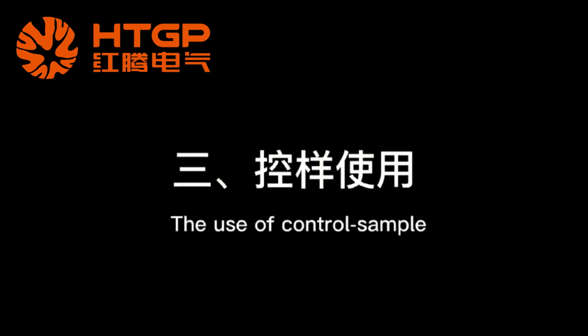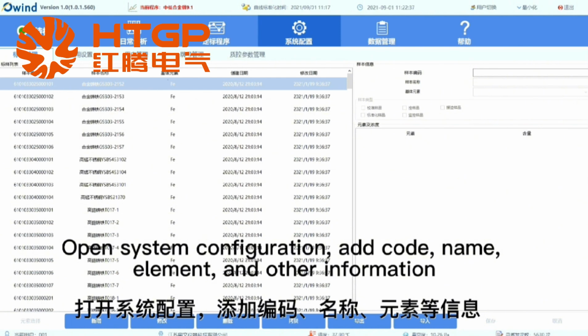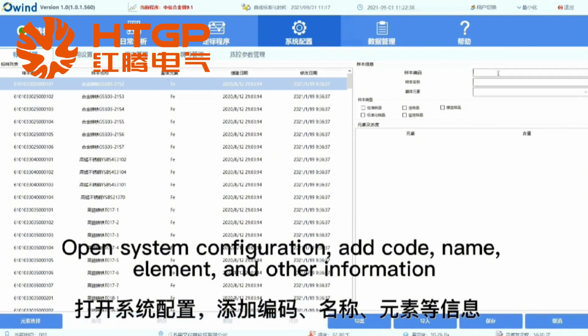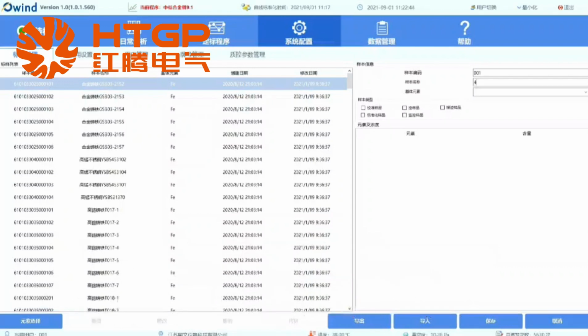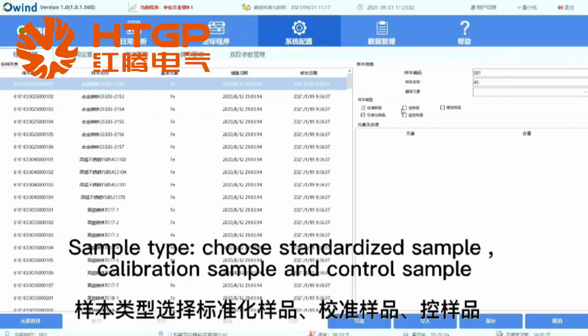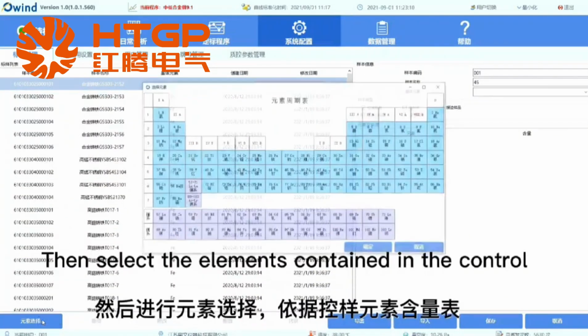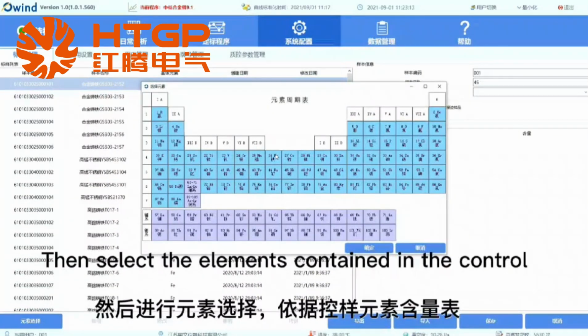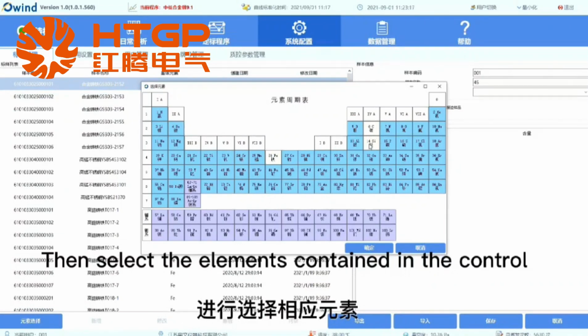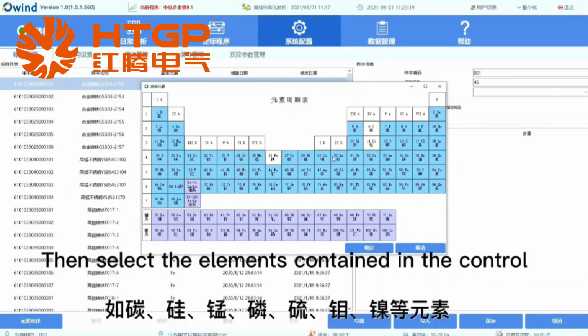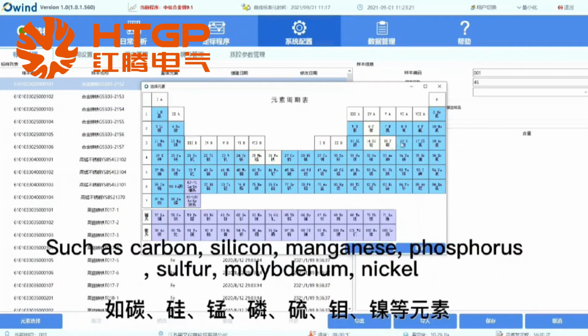The use of control sample. Open system configuration. Add code, name, element, and other information. Sample type. Choose standardized sample, calibration sample, and control sample. Then select the elements contained in the control, such as carbon, silicon, manganese, phosphorus, sulfur, molybdenum, nickel.